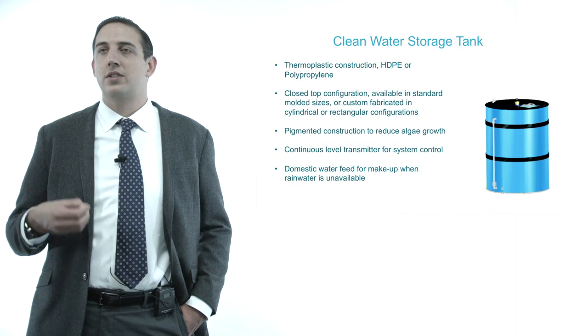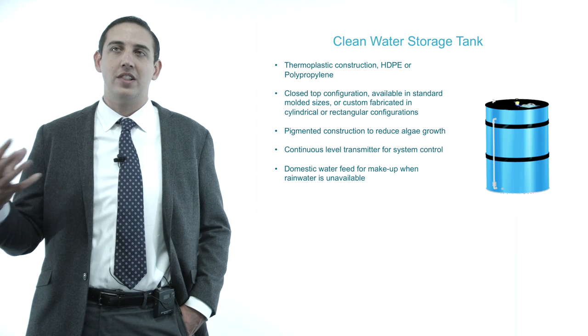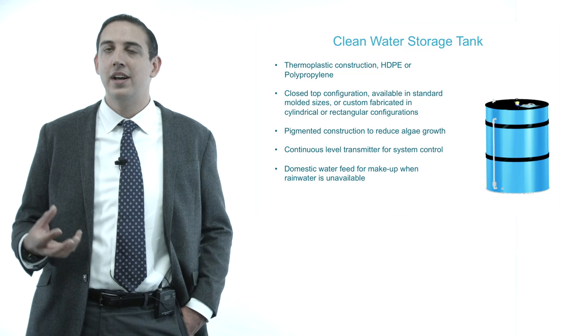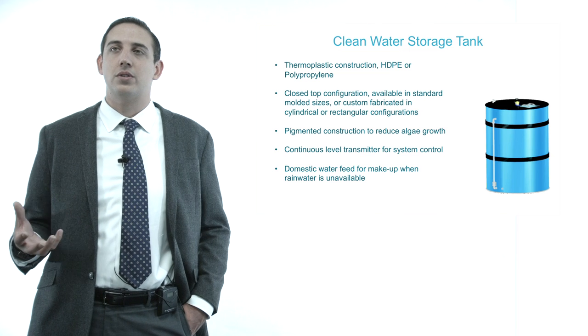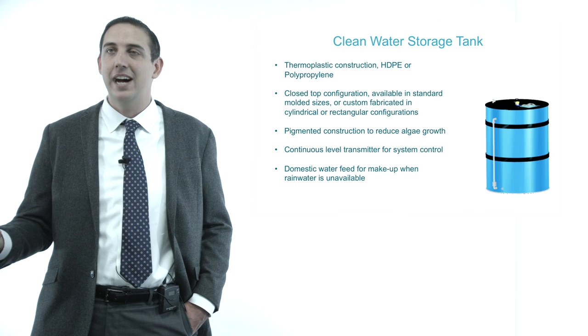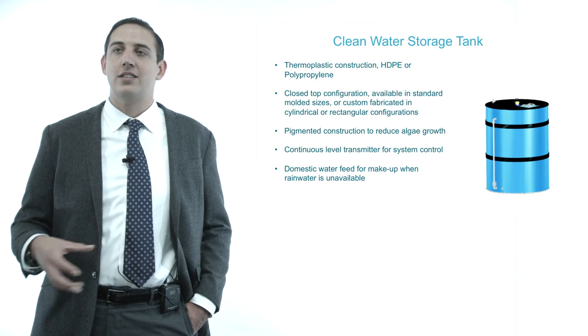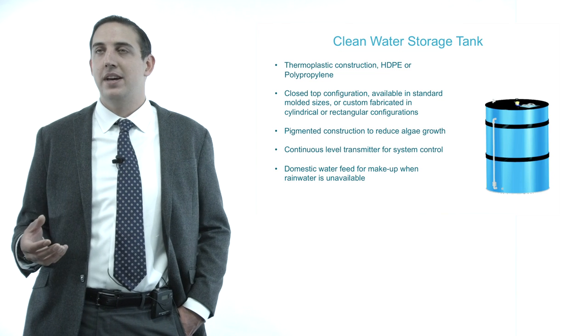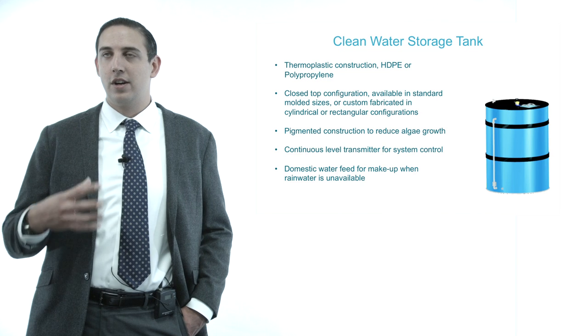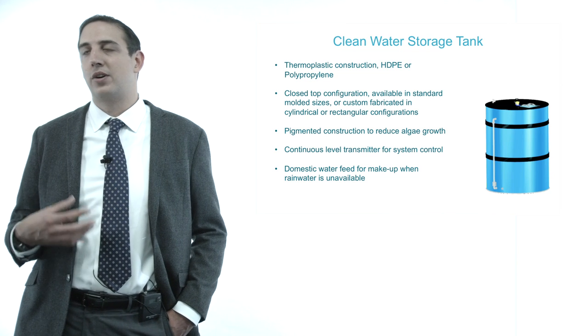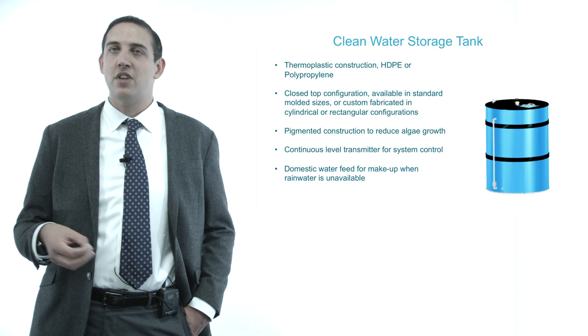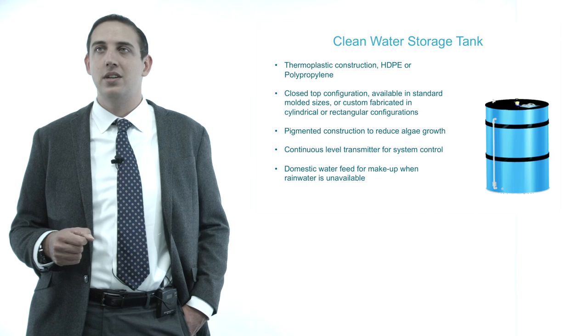In the cistern storage system, you introduce a secondary tank called the clean water storage tank, which serves a similar purpose to the cistern and follows many of the same design rules from session one. It is considerably smaller — whereas a cistern could be 10,000 to 50,000 gallons, the clean water storage tank is typically about 100, 500, or 1,000 gallons. It's almost always located inside, right next to the treatment system. It should always be pigmented to prevent additional bacteria growth from light exposure inside the building. In most cases it is simply a thermoplastic tank — a fairly simple addition to the system.